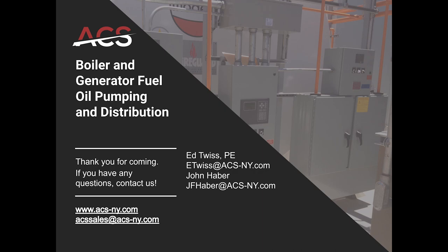And the issue here is, if you buy a generator package that is a UL package, the generators have their own UL packaging, and anything on that generator must have a UL label. So if the belly tank is part of the generator package, you have to have a UL label on that tank. And if you have a UL label on it, then you must use the largest vent opening as the size of your vent termination.